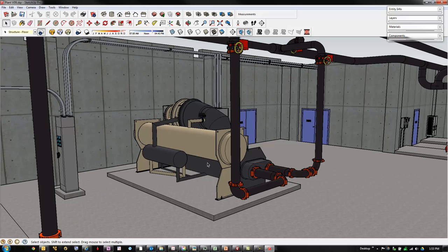You then use the compressor to move that vapor to the condenser, where you have condenser water coming in that's cooler than the refrigerant coming off the compressor. So the process reverses. The refrigerant gives up its energy to the condenser water.